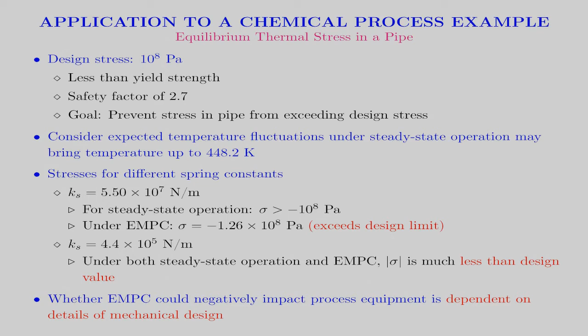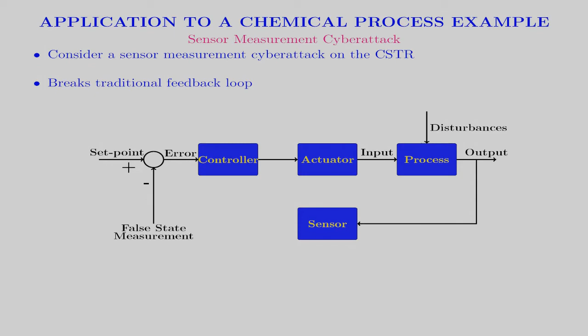a role. To demonstrate how control actions can affect process equipment, a cyber attack that targets the sensor measurement is implemented. On this slide, a typical control loop is shown, with the sensor measurement being compared to the set point to determine the error that is fed to the controller. A cyber attack on a sensor where false state measurements are supplied breaks a traditional control loop. Instead of comparing the sensor measurements to the set point to determine the error, false measurements are compared instead.